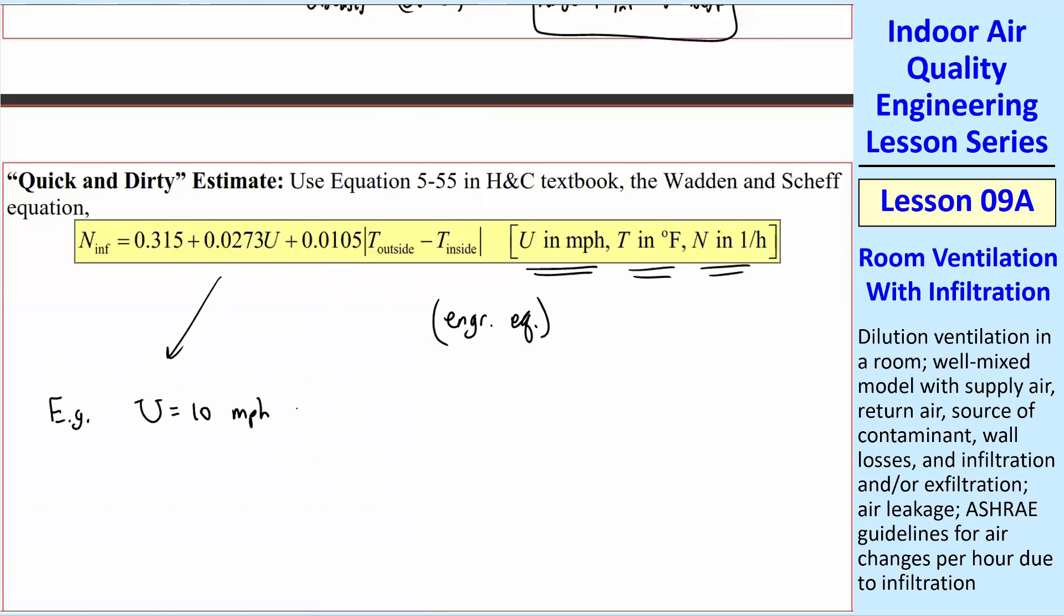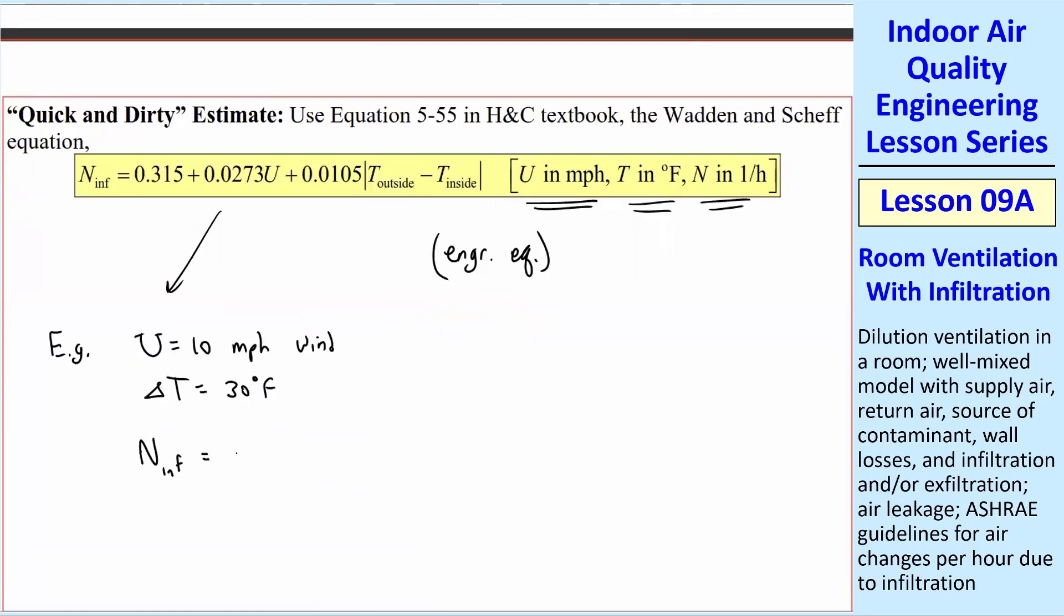Example, suppose we have 10 mile per hour wind, and delta T is 30 degrees F. So this is a typical nice fall weather in Pennsylvania. And so N infiltration is equal to 0.315 plus 0.0273 times 10. You don't put any units in. Just put the numbers plus 0.0105. Notice this is absolute value up here for temperature because they're saying that whether it's cold outside or hot outside compared to inside, you still have some infiltration due to that temperature difference.